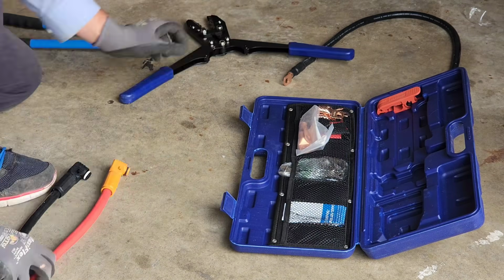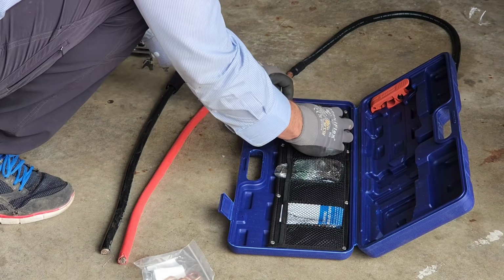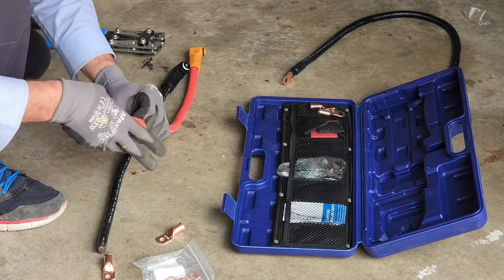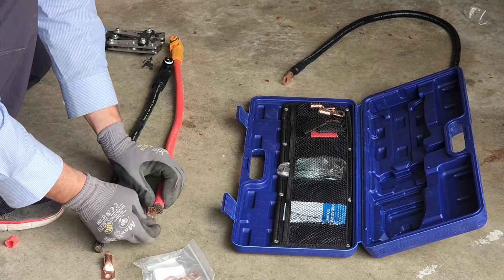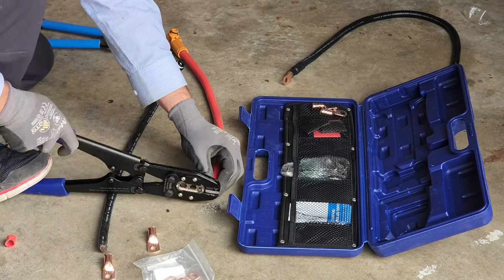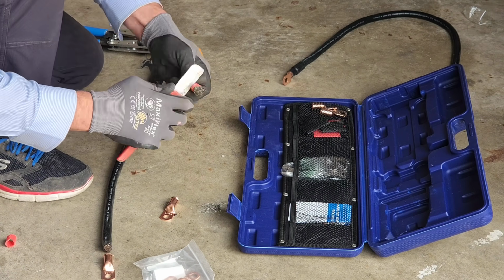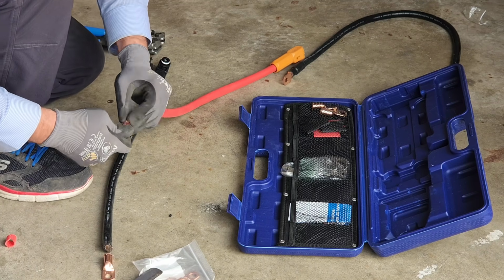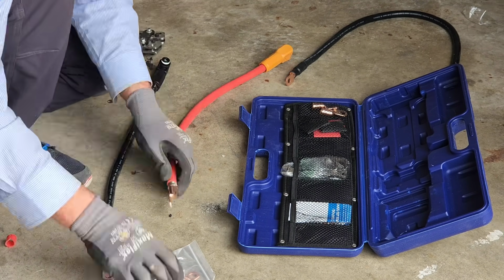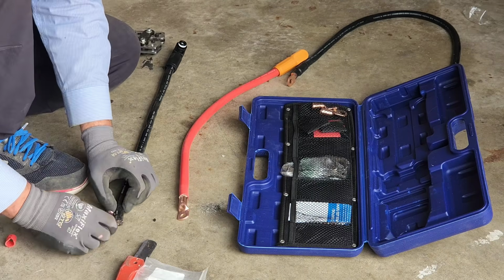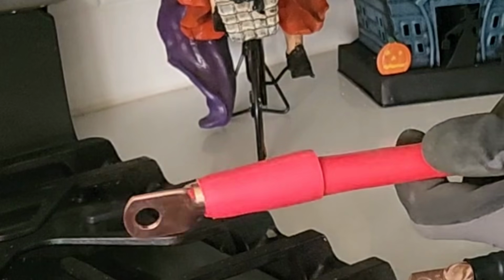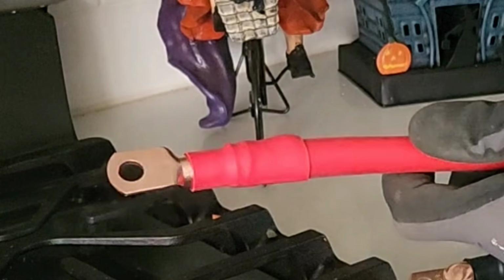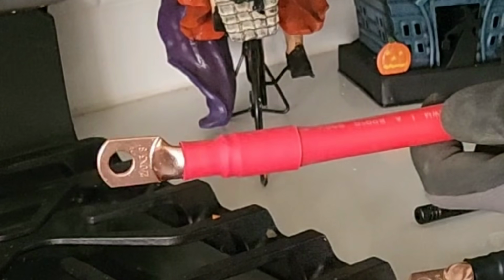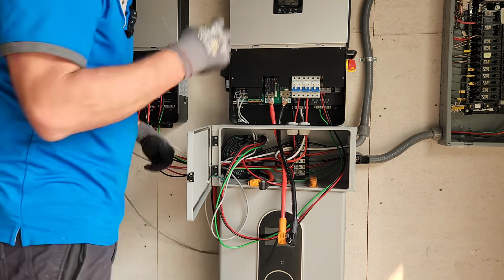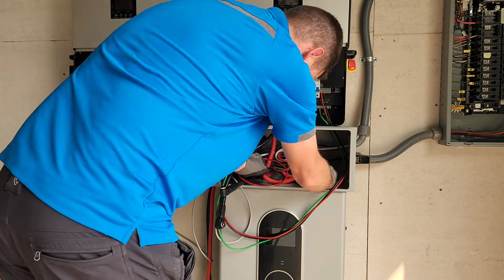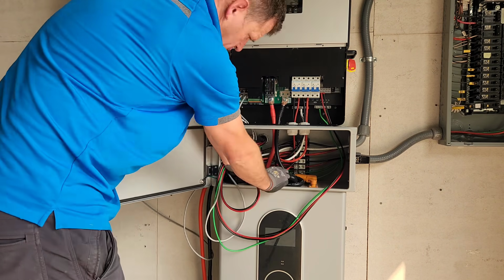Okay, this specific wall mount battery does not come with a battery cable that includes ring terminals. You need to add your own ring terminals because they don't really know what type of inverter you're going to connect the battery to. But I'll include the ring terminals that I used for this project and also a crimper. Make sure these ring terminals will fit your specific inverter you're connecting to. Okay, I'm just connecting the battery cables now here. I also need to connect the battery communication cable to the master inverter.